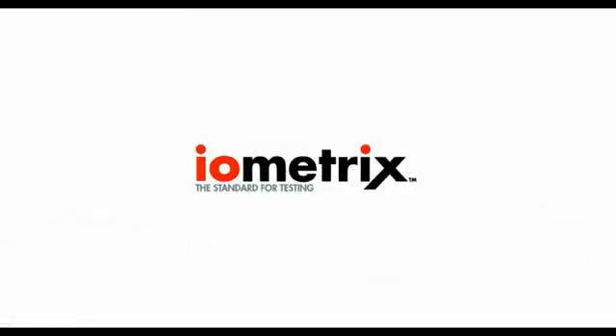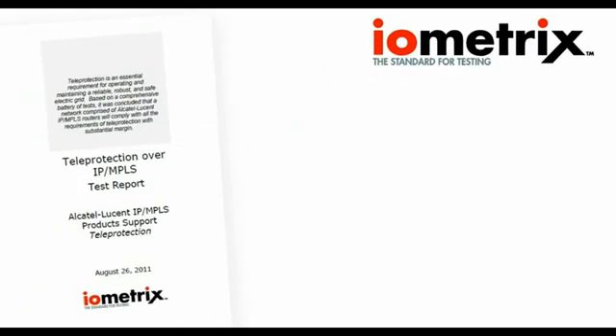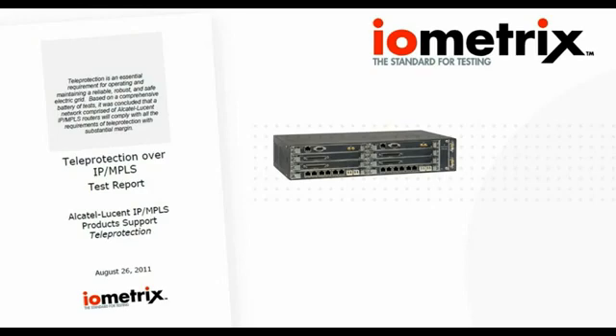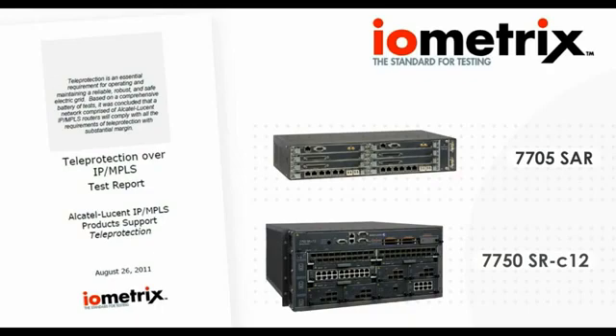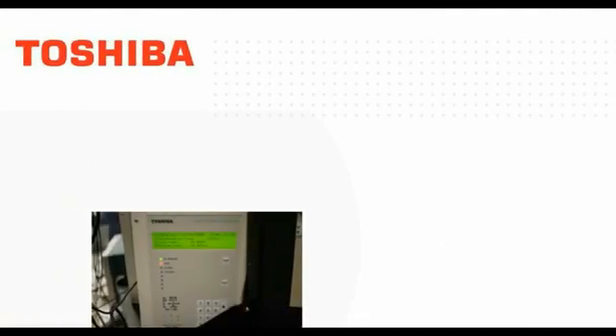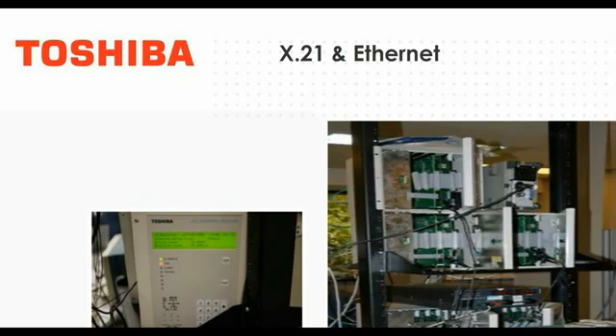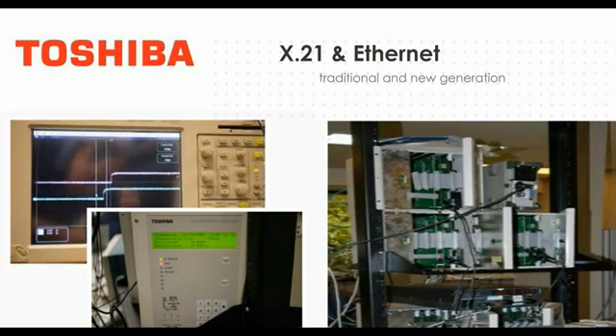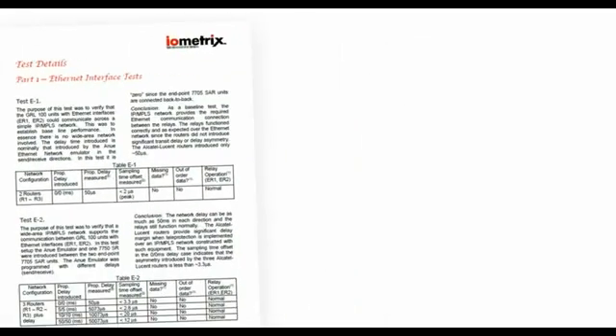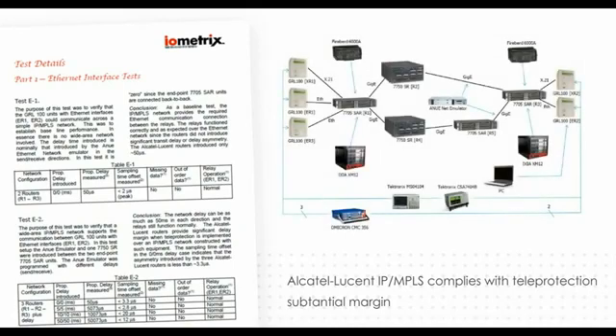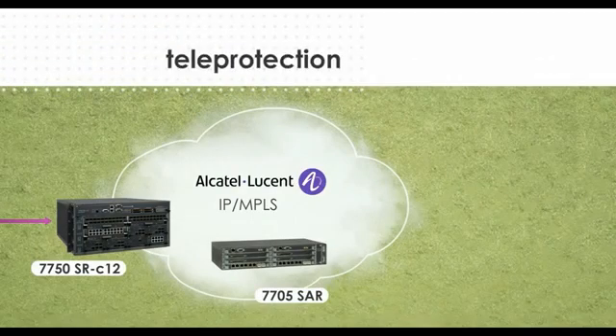Alcatel-Lucent commissioned iometrix, an industry-leading network testing authority, to test and validate the ability of the Alcatel-Lucent IP MPLS-based 7705 SAR and 7750 SR products to support teleprotection. The testing was performed using Toshiba current differential relays available in both X21 interface and Ethernet interface respectively, allowing verification for both traditional and new generation teleprotection relays. Based on a comprehensive battery of tests, it was concluded that a network comprised of Alcatel-Lucent IP MPLS routers will comply with all the requirements of teleprotection with substantial margin. The IP MPLS network performed well within the requirements of the teleprotection application that has, to this point, only been supported by TDM networks.